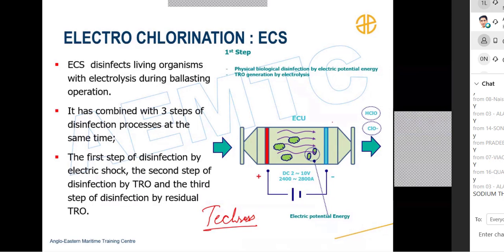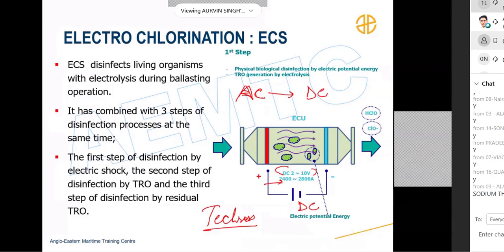And seawater is a good conductor. So this electrical current is a DC current. On ship we are making AC. So AC first will be converted to DC with huge rectifier units, and the current value is also very high, easily more than 300 amps. But the voltage level is very low. You can see the voltage level and see the current level. So this depends. So there it is.